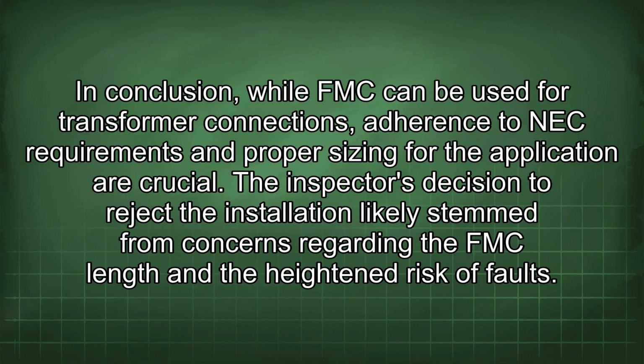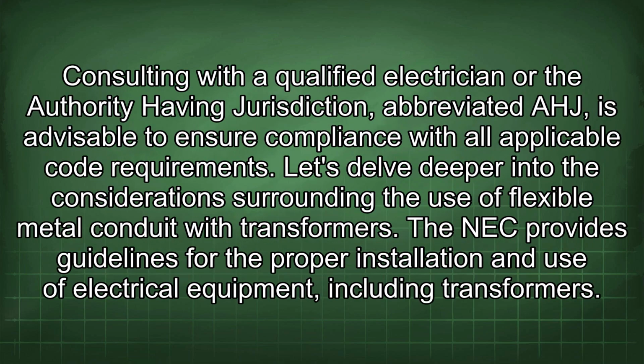In conclusion, while FMC can be used for transformer connections, adherence to NEC requirements and proper sizing for the application are crucial. The inspector's decision to reject the installation likely stemmed from concerns regarding the FMC length and the heightened risk of faults. Consulting with a qualified electrician or the authority having jurisdiction, abbreviated AHJ, is advisable to ensure compliance with all applicable code requirements.